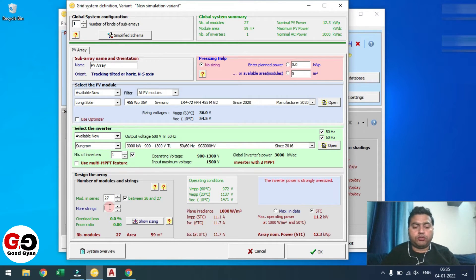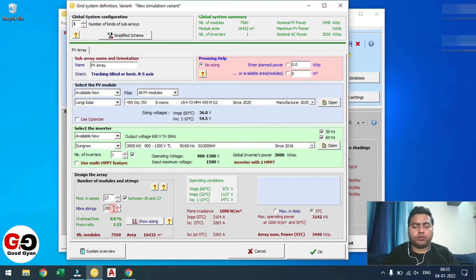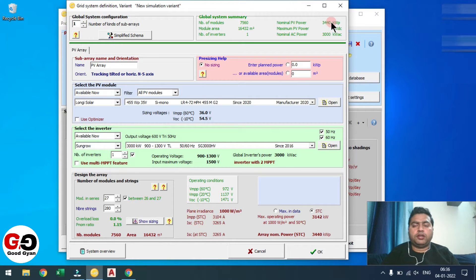For strings, I am going to select 210. With 210, the overloading is coming around 86%, so let me increase it a little bit to 280. With 280, the overloading is coming at around 15% and loss is 0.0%. So your total modules are 7560 — DC capacity 3.44 megawatt, AC capacity 3 megawatt, and the area is 16432 square meters.